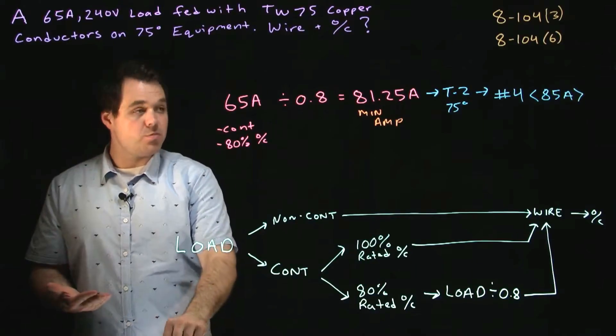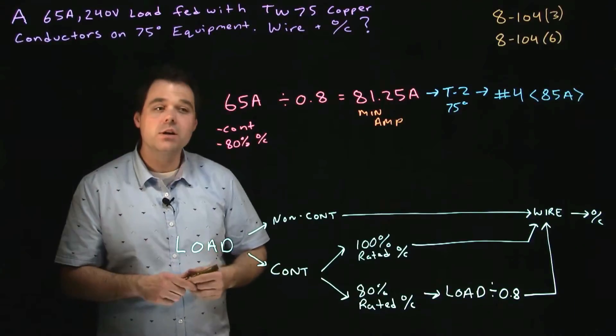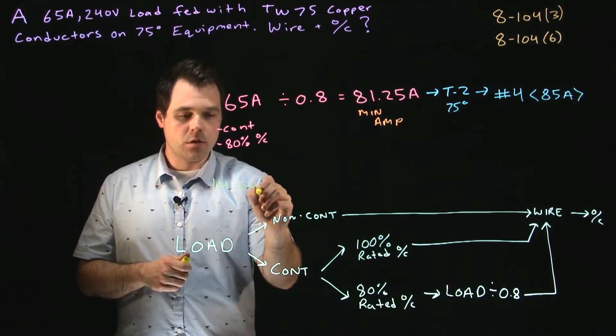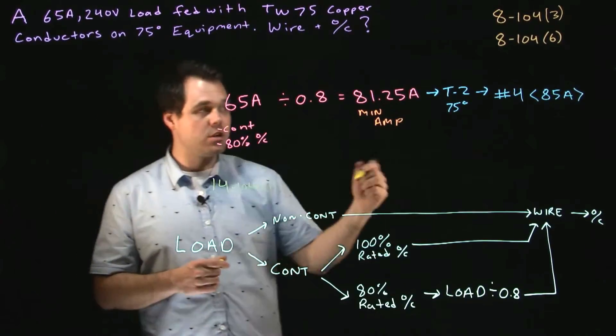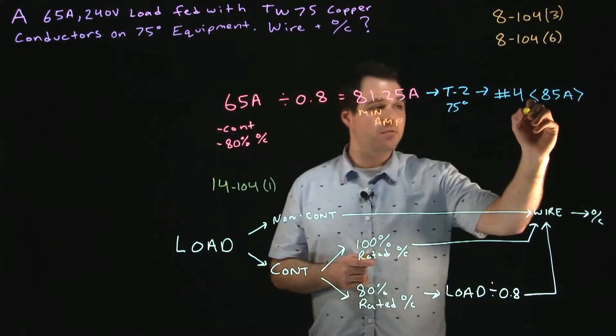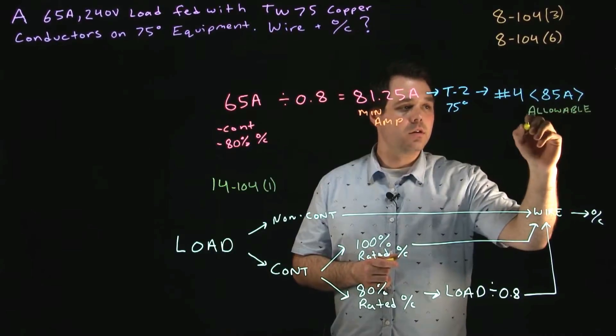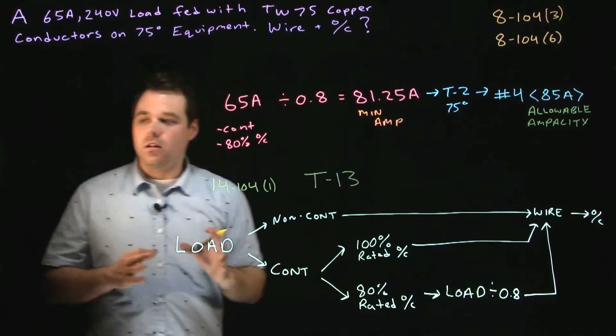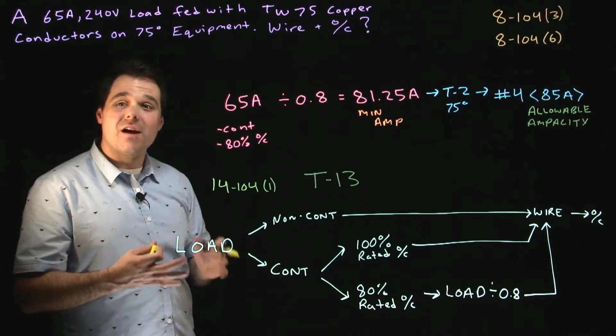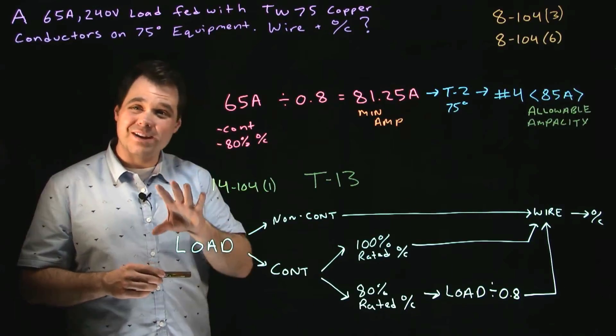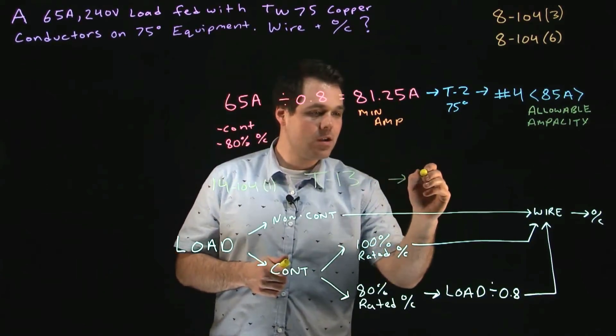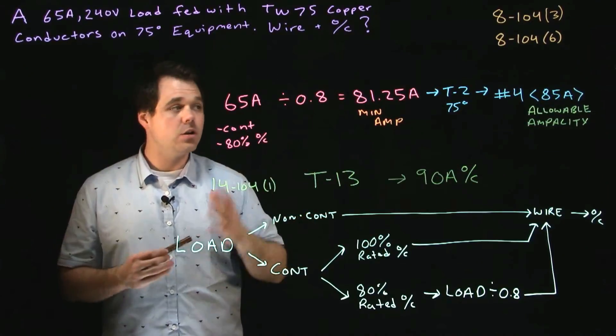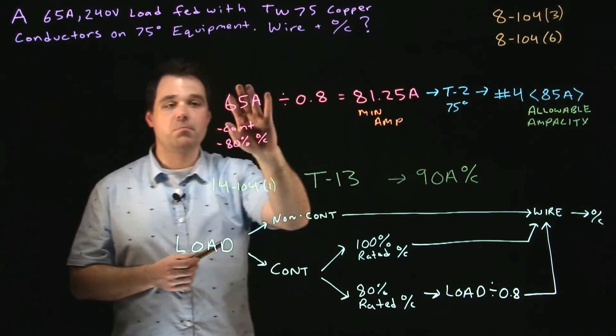The next step after sizing the wire is to size the overcurrent device. We apply 14.104, Subrule 1, which tells us to take the allowable ampacity of the wire — 85 amps — to Table 13. On Table 13 there is no 85-amp overcurrent device available, so we look at the ranges and find we need a 90-amp overcurrent device on this wire. A 90-amp OC is set by code to protect our number 4 wire rated at 85 amps, which is definitely large enough for the 65-amp load.